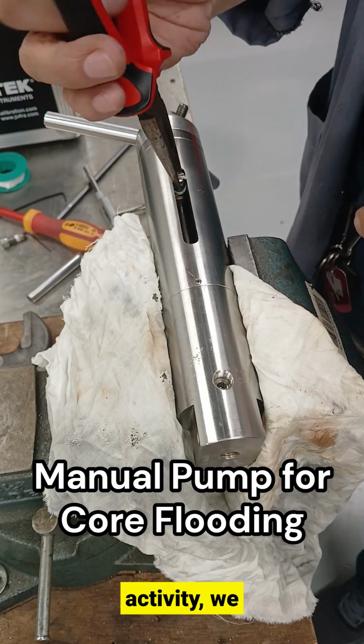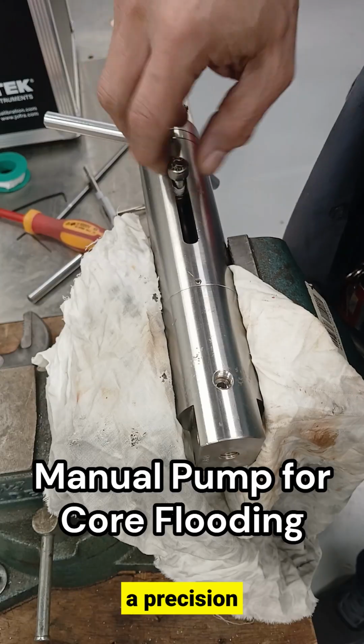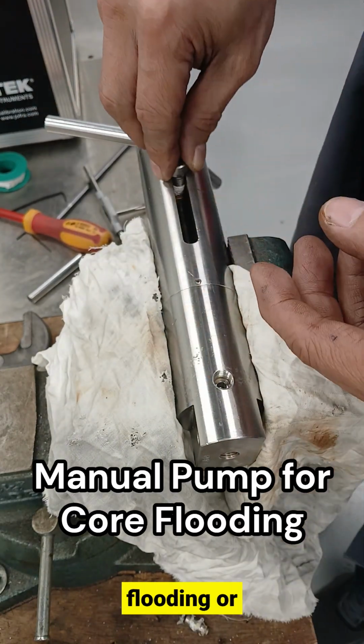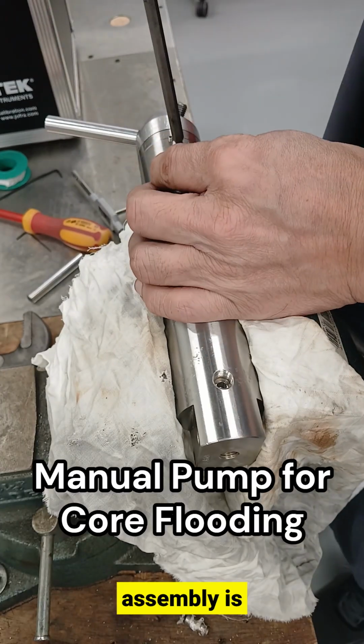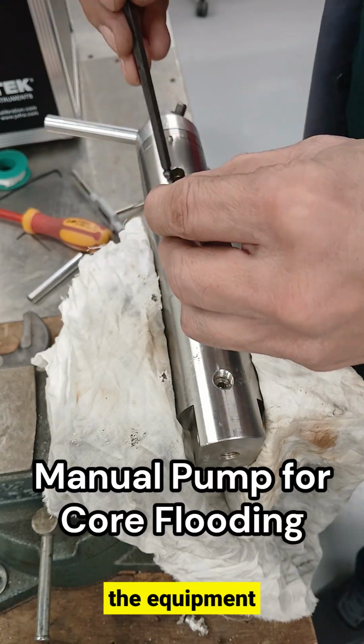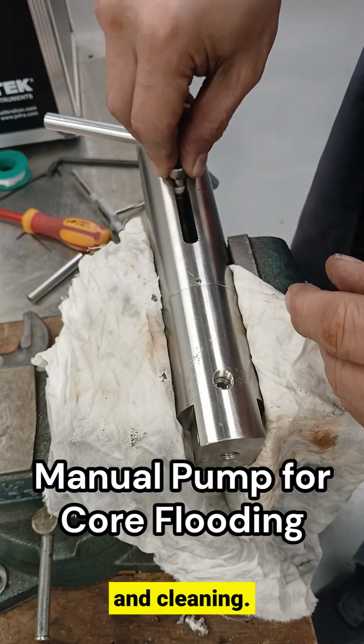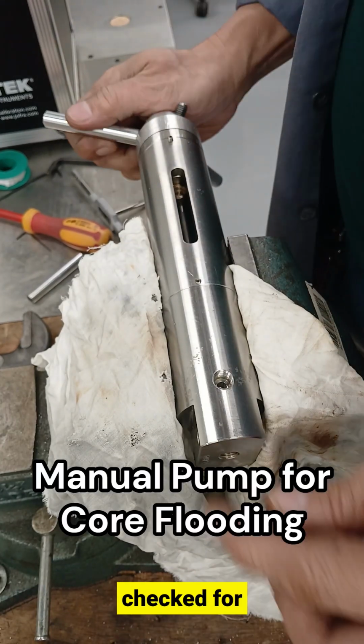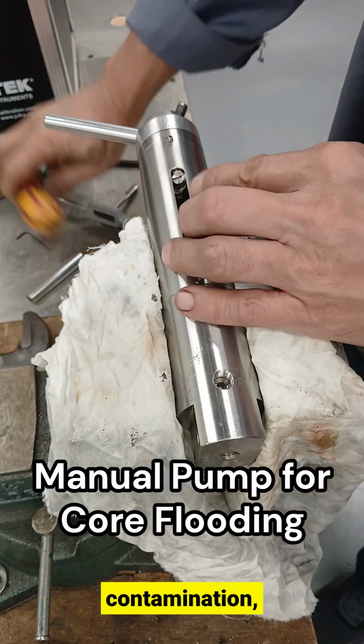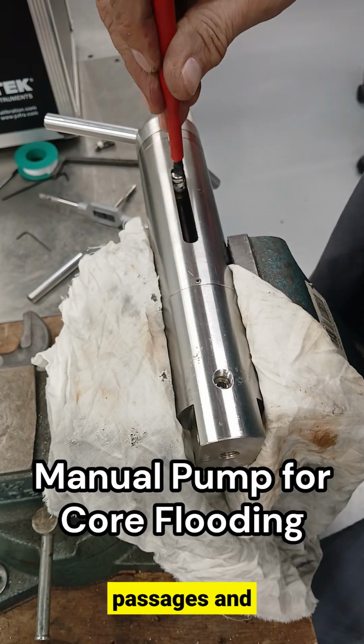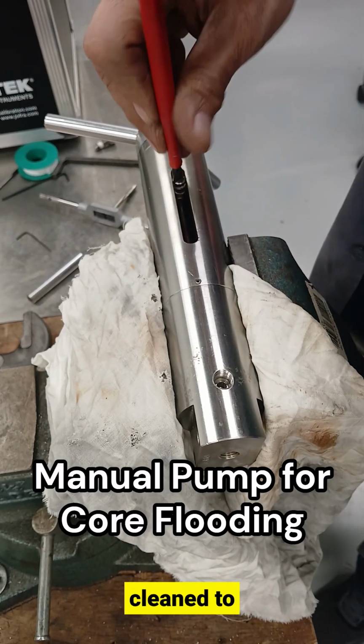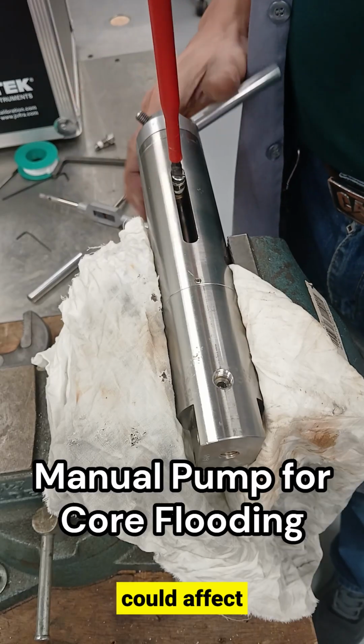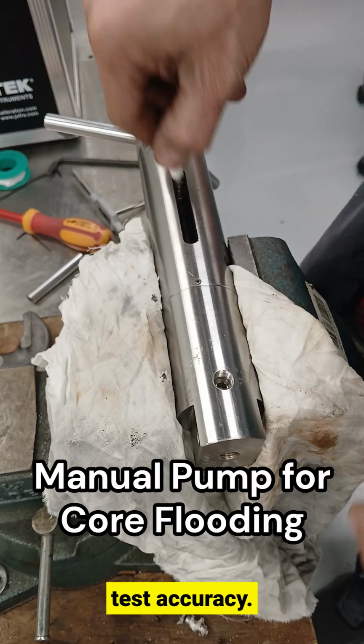In this activity, we are inspecting and servicing a precision stainless steel laboratory component used in a core flooding or fluid flow testing system. The assembly is carefully removed from the equipment for maintenance, inspection, and cleaning. The component is visually checked for signs of wear, corrosion, contamination, or mechanical damage. All internal passages and sealing surfaces are cleaned to remove any debris that could affect fluid flow or test accuracy.